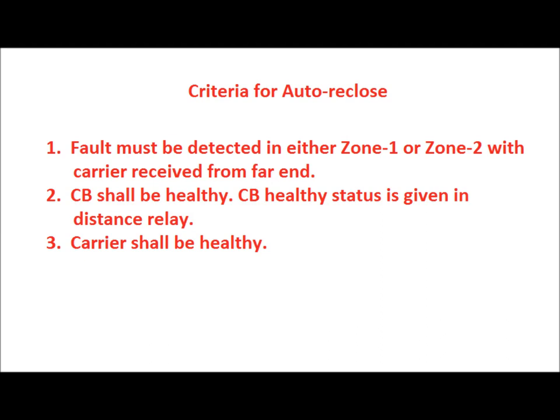The criteria for auto reclose are: (1) the fault must be detected in Zone 1 — if it is Zone 2, carrier-aided protection trip is required for successful auto reclose from the distance relay; (2) the circuit breaker shall be healthy, with CB healthy status given as a binary input to the distance relay; (3) the carrier shall be healthy; (4) master trip relays shall not be operated; (5) LBB and bus bar protection shall not be operated; and (6) the auto reclose switch shall be in the enabled position.